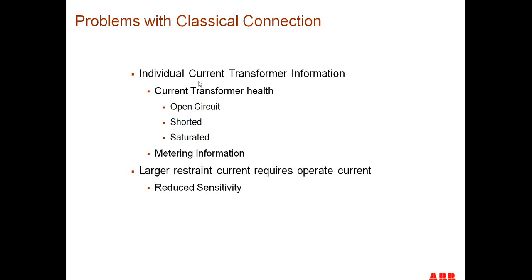What this does is that we lose a lot of current transformer information. We don't know if either one of those two current transformers is short-circuited, if either one of those two current transformers is open-circuited, or there may be saturation occurring in one of the current transformers, nor do we know any information about the metering information.